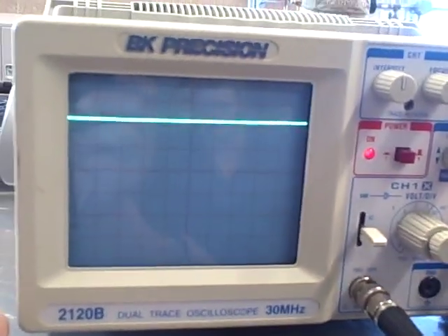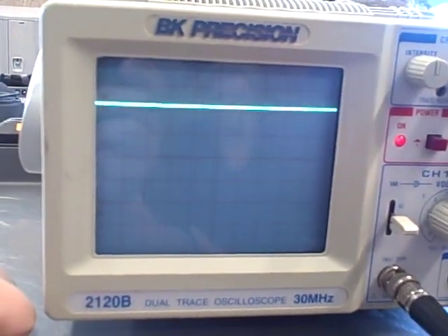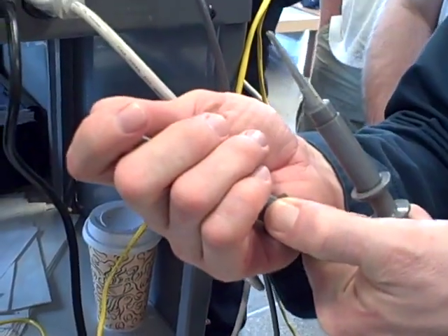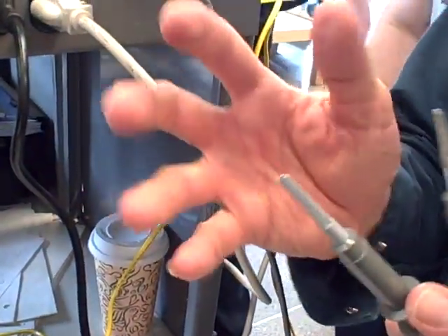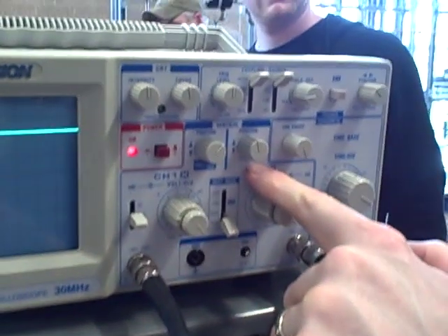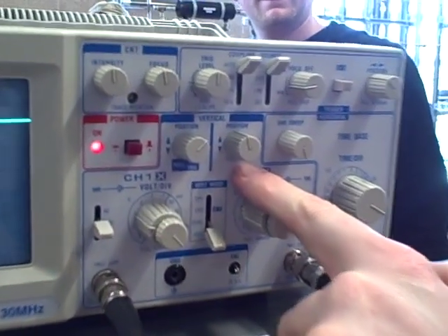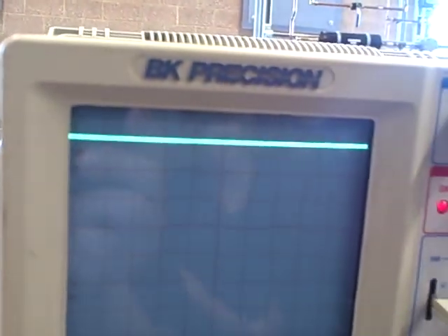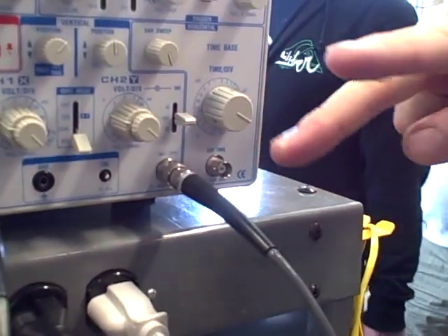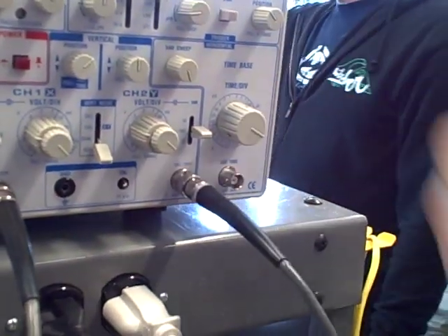What this does in the ADD mode is it takes whatever voltage I have on one channel and adds it to the voltage on the other channel. We're going to throw one more twist in here. We're going to come over here, and on this particular scope there's a setting right there called INVERT. I'm going to pull that out. What that means is whatever signal comes in channel 2 is going to be made upside down.